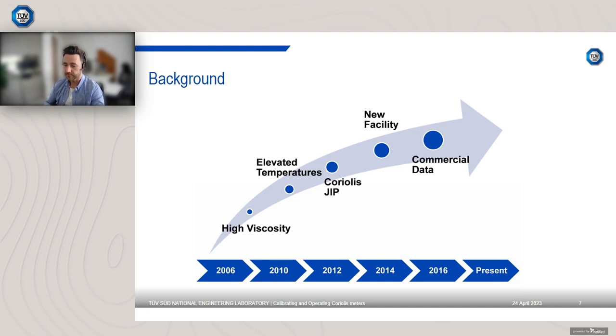So back in 2010, a lot of customers were starting to ask us, is there a temperature effect? We are now operating at 60, 70 degrees Celsius, but we're only calibrating at 20 degrees Celsius. Is there potentially a temperature effect? So we conducted some experiments at NEL and showed there was potentially a temperature effect, maybe not as significant as viscosity, but a temperature effect nonetheless. And we wanted to explore pressure. So we created a Coriolis JIP in 2012. I led that for the 2 years. We completed that project successfully, and we found that yes, there was indeed a pressure effect, in addition to the already known viscosity effect, and potentially a slight temperature effect.